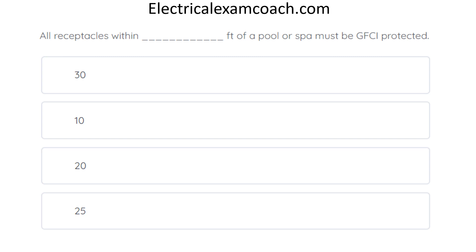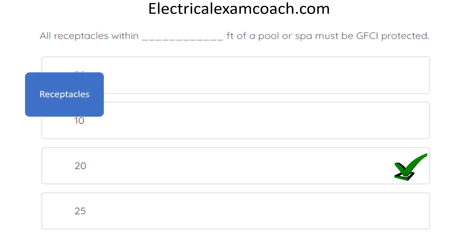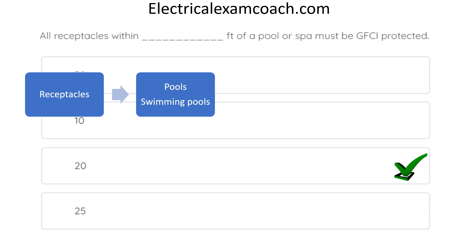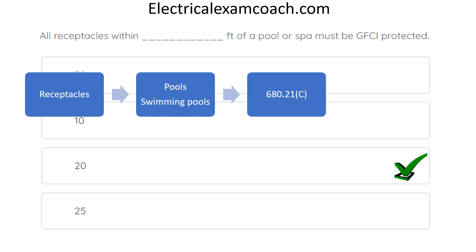All receptacles within blank feet of a pool or spa must be GFCI protected. The correct answer is 20 feet. We use our keyword and index process — we're talking about receptacles, so we head to R in the index. Under its subheading we look for pool, spa, or GFCI protection. We don't find 'pools' but we do find 'swimming pools,' which lists several code articles. The first one sends us to 680.21(C), depending on your code cycle. The heading is about GFCI protection, but scanning the paragraph, it's not what we're looking for.